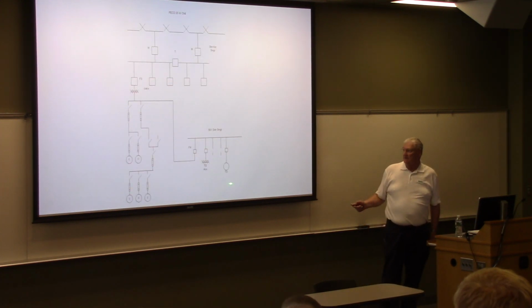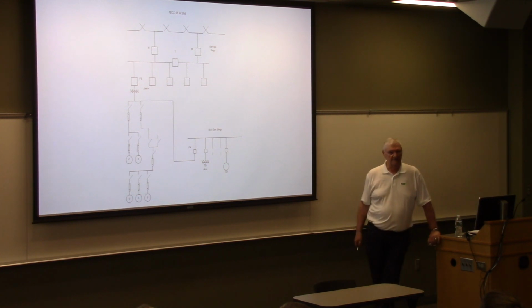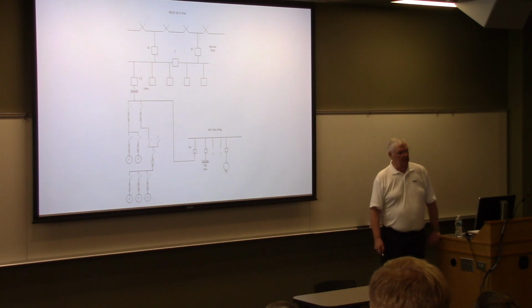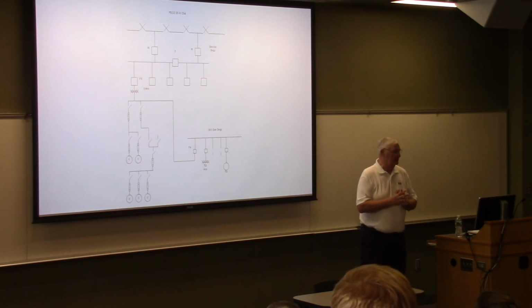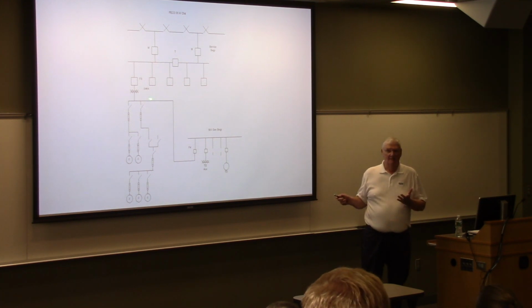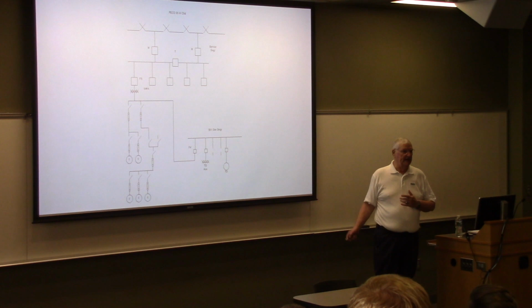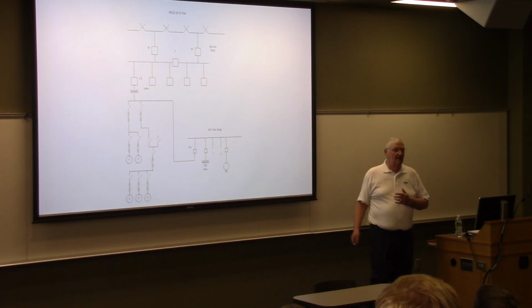This is a 5 kV bus, turbine generator, 4.5 megawatts, heat recovery from the exhaust gas. 5 MVA transformers here, and this one was put in for this bus. Originally, it was a delta-Y transformer, but the utility company said we only allow YY connections. So they pulled out a 5 MVA transformer, 60, 70,000 pounds, and replaced it with a YY connected 5 MVA transformer, fired the system up, and took the system offline because the generator was a 4/5 pitch machine.